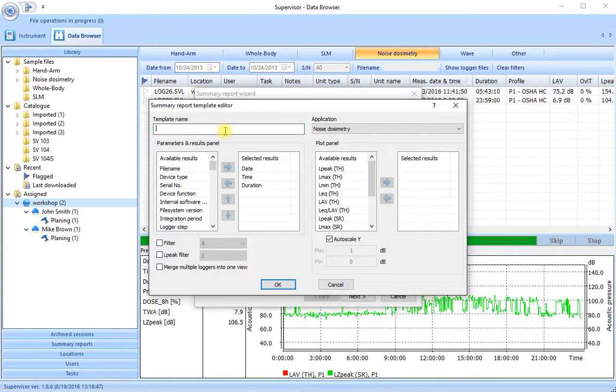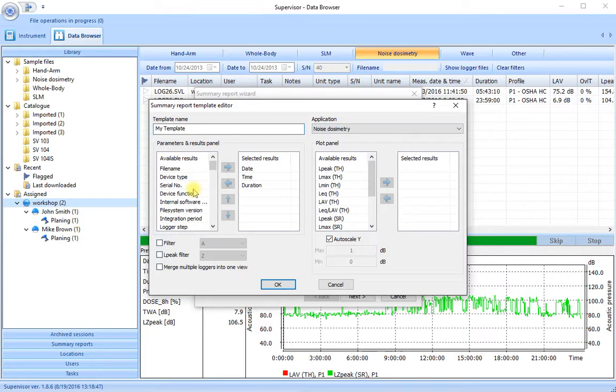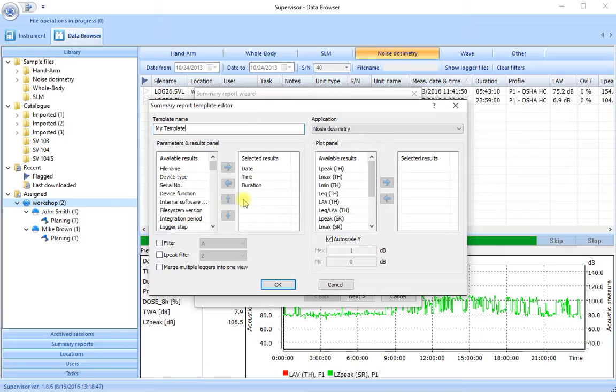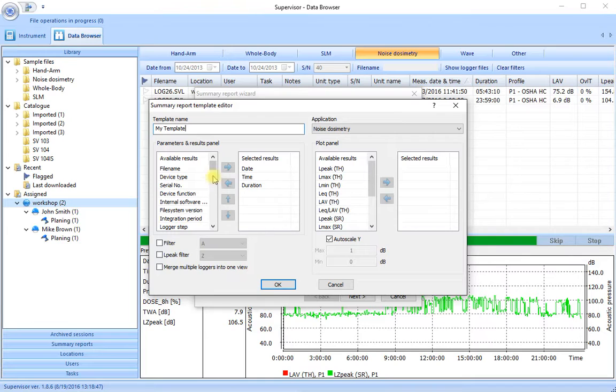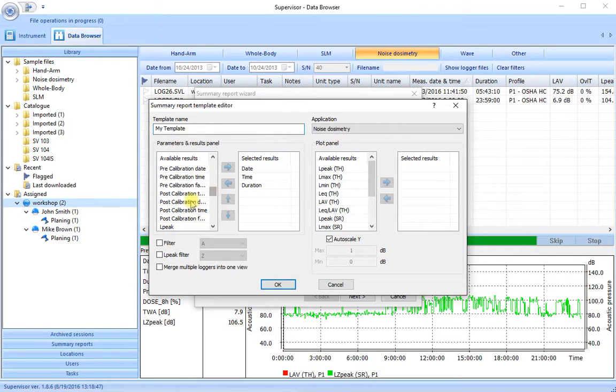We give the template a name. My template for example. And make sure that the application chosen matches our measurement that we want to look at. So noise dosimetry. This side represents the information that we'll see in text format. So these are the available results. These are the currently selected results. The date and time of the measurement, the duration of the measurement. We want a little bit more information than that so let's go down and look at the information that may be significant here.